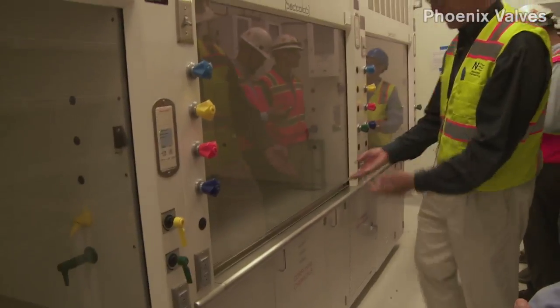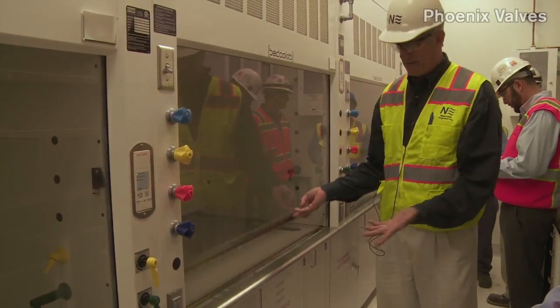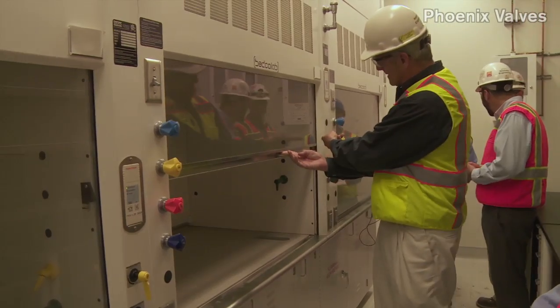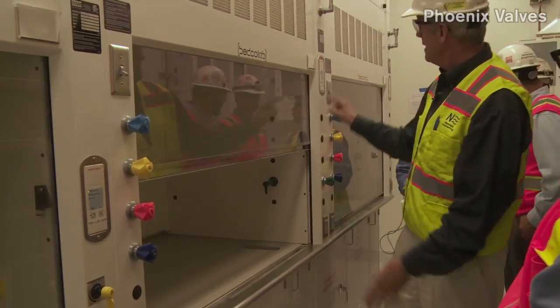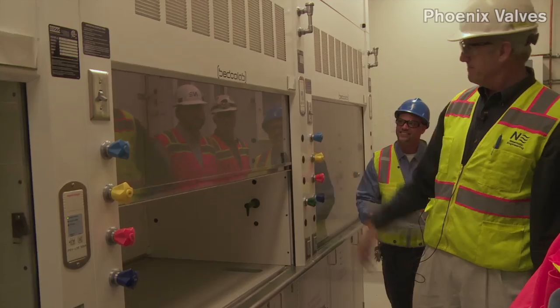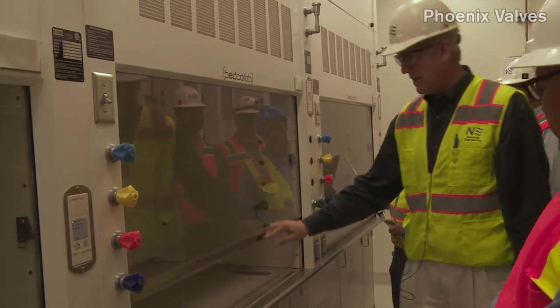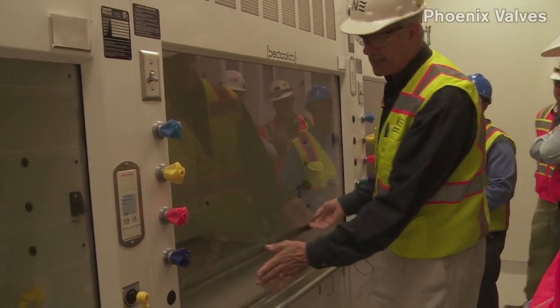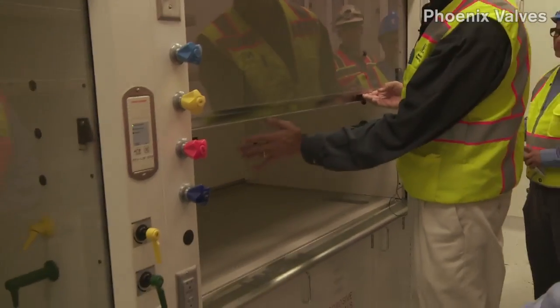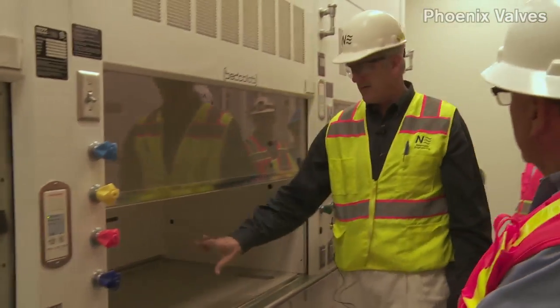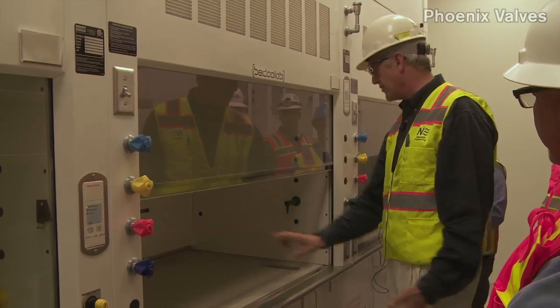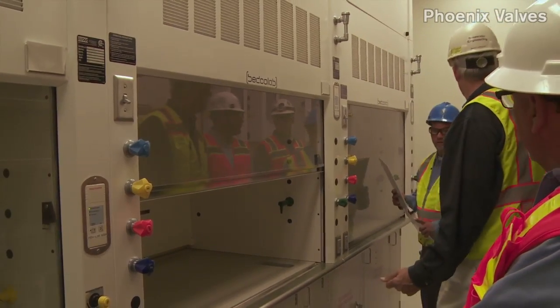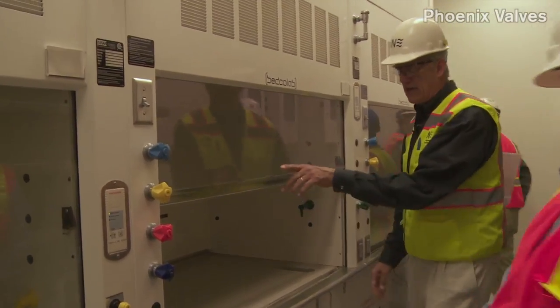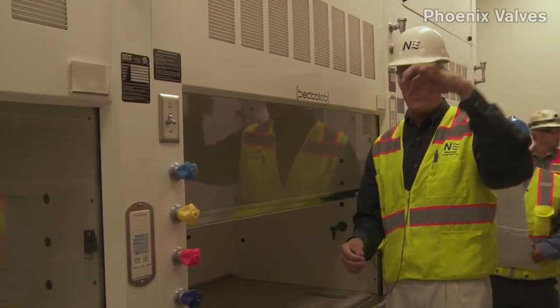With the fume hood, you want to be able to raise the sash, and it hits this sash stop at 18 inches. The light should be green all the time. So you raise and lower the sash, the user's using it, they have 100 foot per minute capture velocity. If you have a meter, you could measure that. Are there any Kim wipes in this lab? Not yet. There's these Kim wipe tissues that the researchers use.